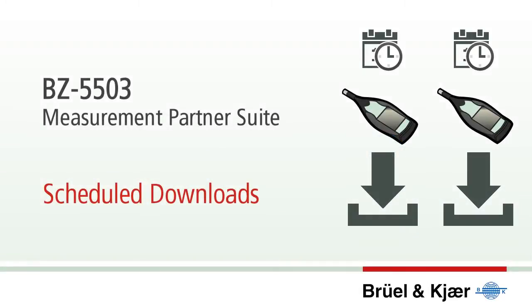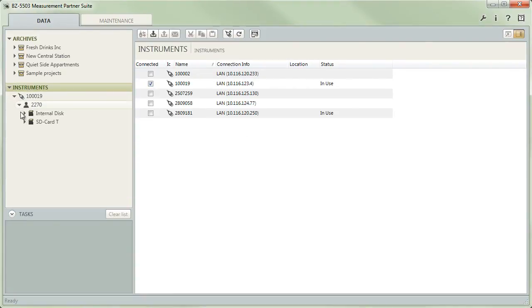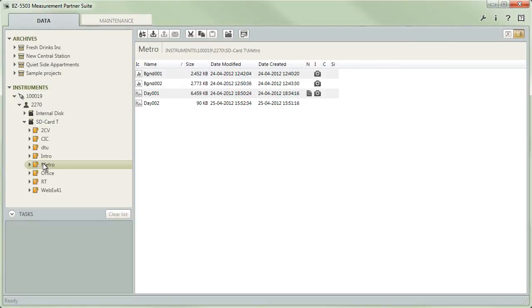You can set up Measurement Partner to automatically connect to your handheld analyzer at regular intervals and pull data from the instrument. You can schedule several tasks for the same or different instruments. To schedule such downloads, connect manually to the instrument, select the user account, disk or folder on the device from where new data should be taken, and click the To Archive button.